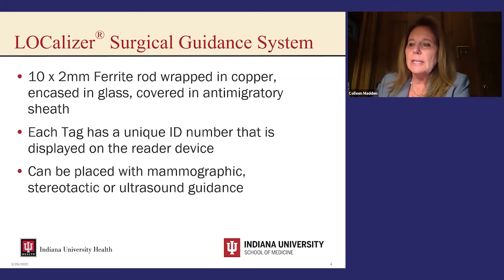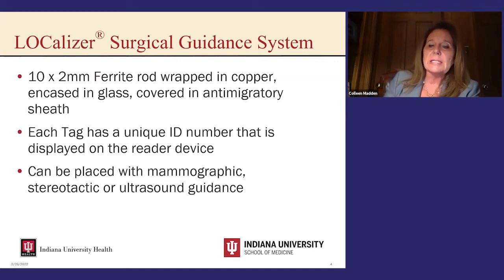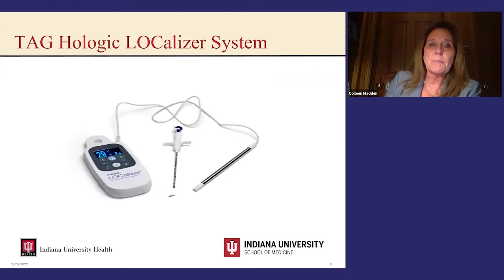And what is it? Well, it's a wireless radio frequency identification system that is used for wireless localization. There's a radio frequency chip, which is encased in a 10 by 2 millimeter ferrite rod, which is wrapped in copper and encased in glass. This glass is covered in an anti-migratory sheath that is placed in the breast. Each tag has a unique ID number that is displayed on the reader device. And this tag can be placed with mammographic, stereotactic, or sonographic guidance.